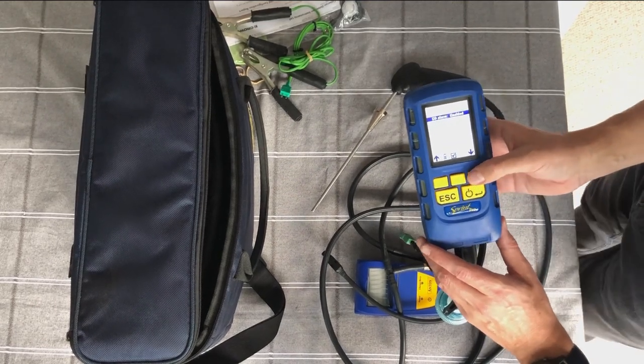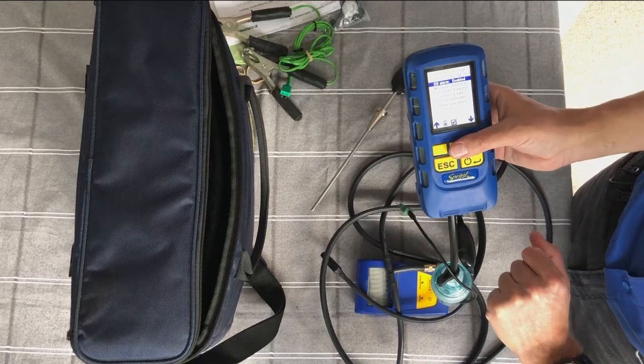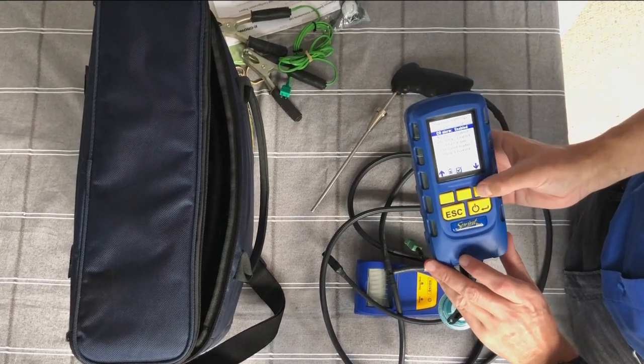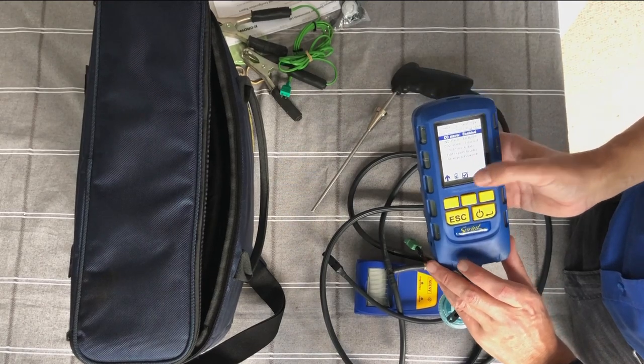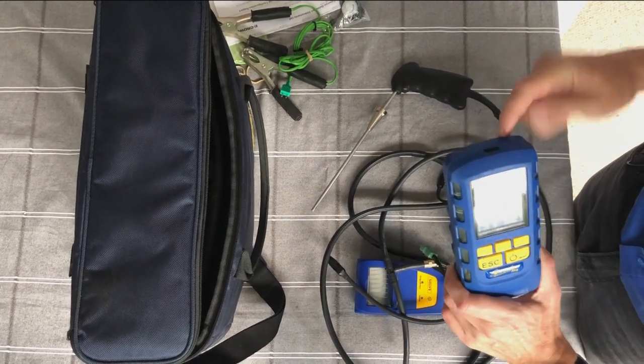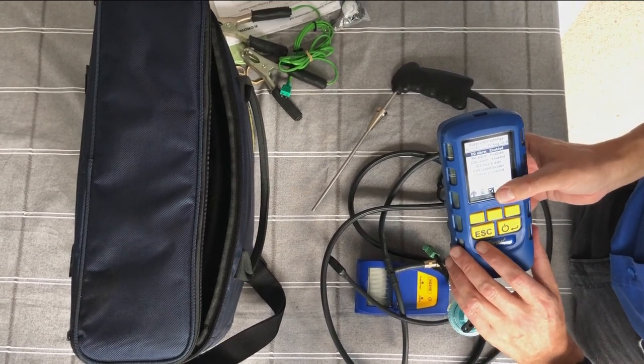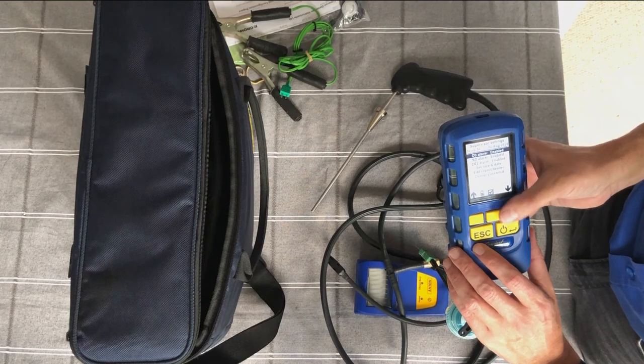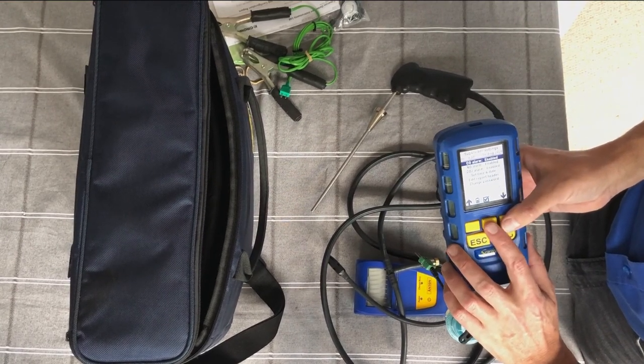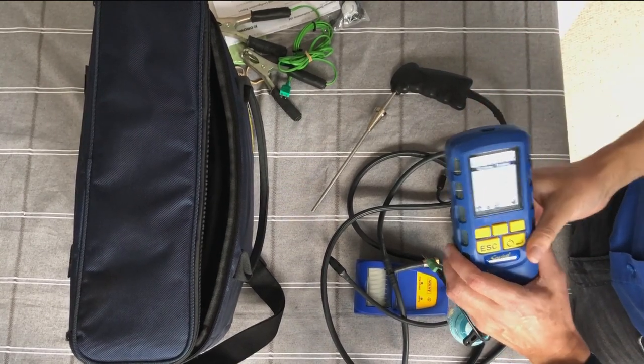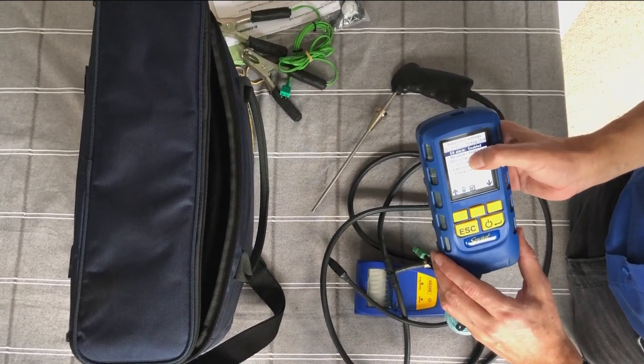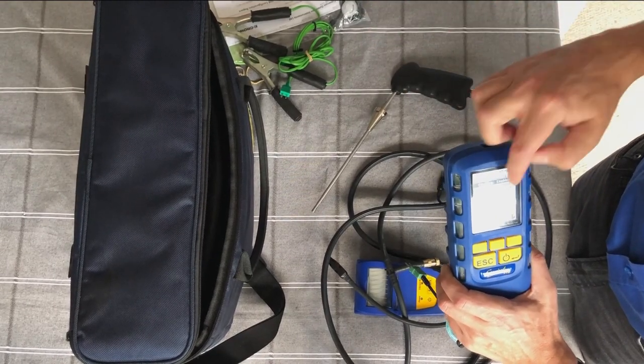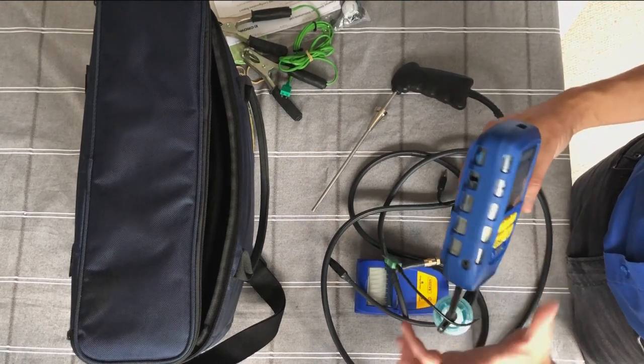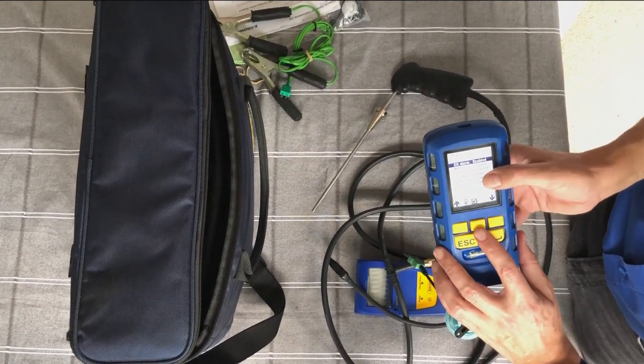Supervisor settings. Depending on the settings, some companies will lock these supervisor settings, but that allows you to turn on and off the inbuilt personal alarms in these. Now, don't rely on this as a personal alarm because it isn't. But it will warn you if there's high levels of CO, NO, or CO2. I've got all mine enabled, but if you're finding those annoying, because sometimes I've got a NOx version here, more of a commercial analyzer, it will alarm because the NOx is so toxic. Levels that are permitted in flue gas, you wouldn't want to breathe, but it does alarm you to let you know that it's exhausting quite high levels of NOx. But you can turn those on and off there.